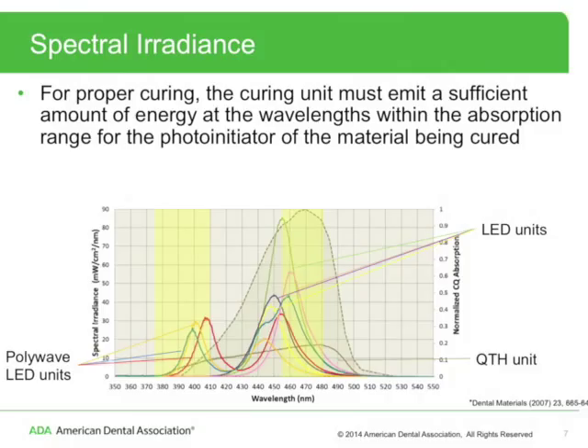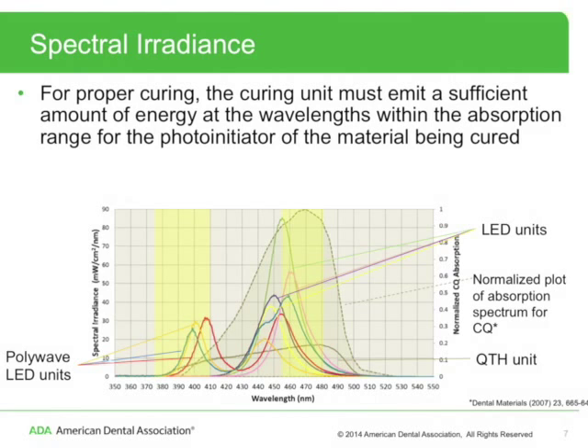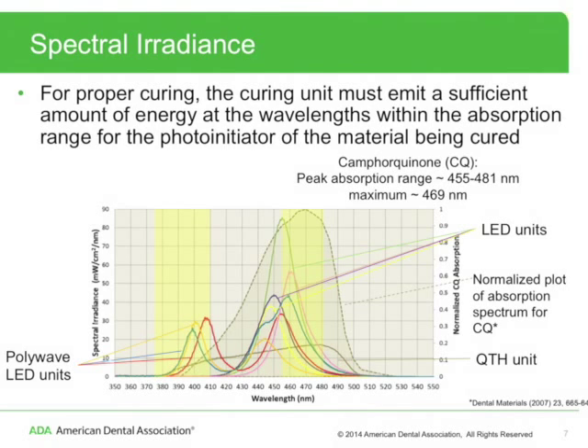This figure displays the spectral emission plots for different LED and quartz tungsten halogen curing units, along with a normalized plot of the absorption spectrum for camphorquinone. Camphorquinone is the most commonly used photo initiator in dental resin formulations. The region shaded in yellow, from approximately 455 to 481 nanometers, is defined as the approximate peak absorption range for camphorquinone. In general, the greater the percentage of the spectral emission curve for a curing unit that overlaps the peak absorption range for camphorquinone, the better.